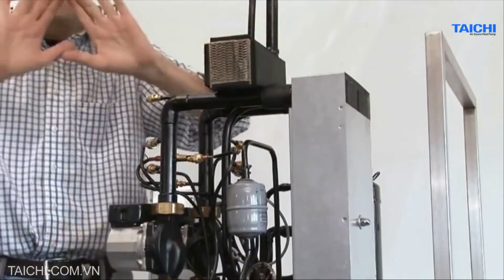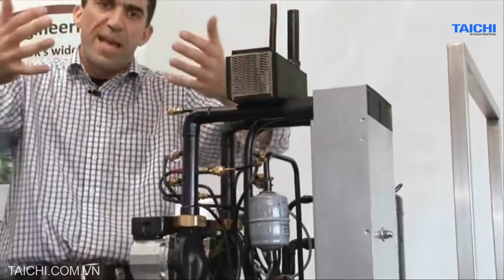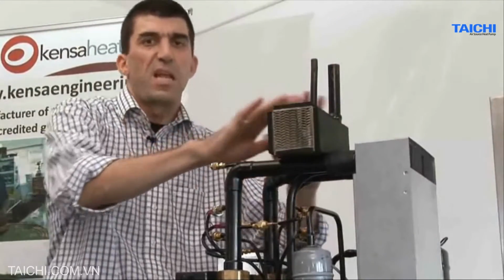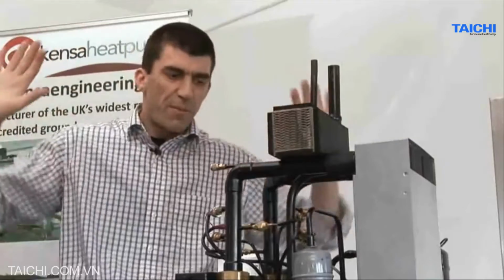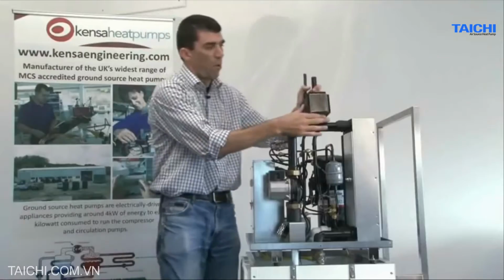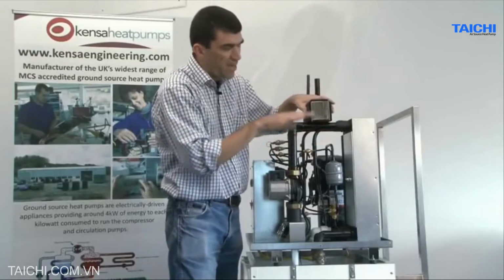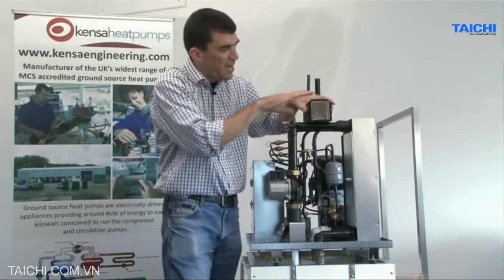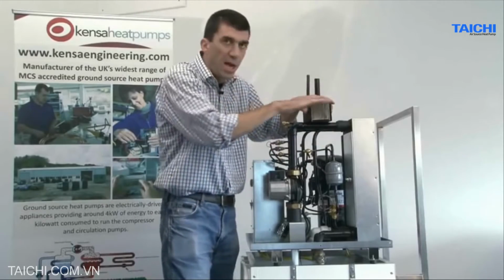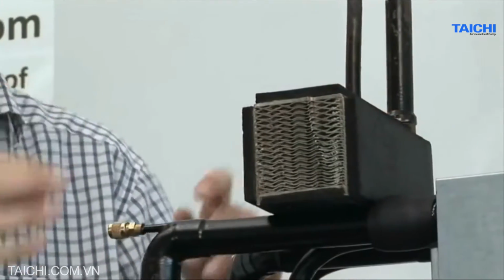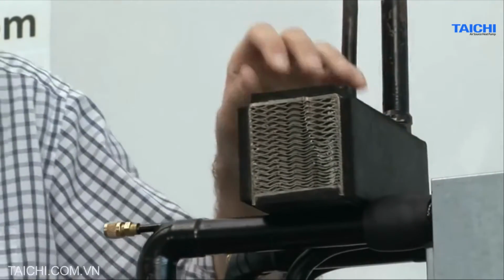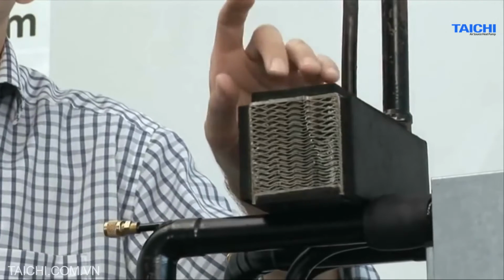The heat exchanger gives you a big surface area for heat transfer between the water, or maybe the water and the glycol, and the refrigerant gas. We'll come back to the gas, but really all this does is condense something with a big surface area into a small compact little device. I've got one here that's sawn in half, and when it's in operation, if you could see inside it, it'll have a layer of water, a layer of gas, a layer of water, a layer of gas. And it gives you this big heat transfer area in a nice compact little unit.